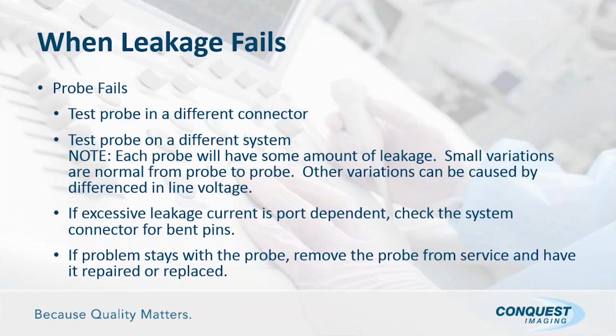If excessive leakage current is port dependent, it's obviously a system problem, and you should check the connector for bent pins. You can check the probe. Do a thorough inspection of the system, because it's obvious that if you change ports and the value changes, there's a problem with the system. If the problem stays with the probe, remove the probe from service and have it repaired or replaced.